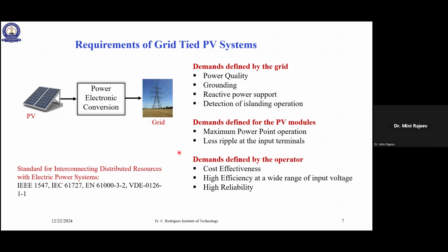Okay, that needs to be detected because suppose the grid fails and in that section the grid power is not there. Some operator or somebody who is working on that inverter side of the PV will get a shock, or somebody who is coming for grid maintenance, not at the inverter side of PV, will get a shock if the inverter is still supplying power to the grid. So that is what islanding operation means.